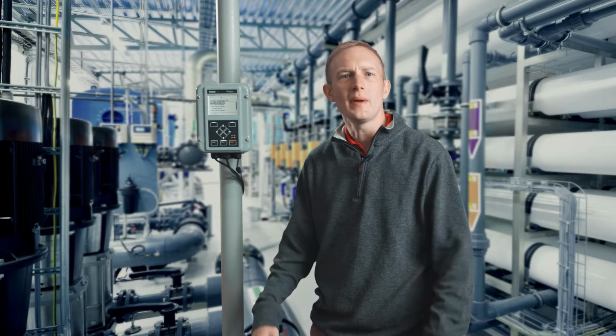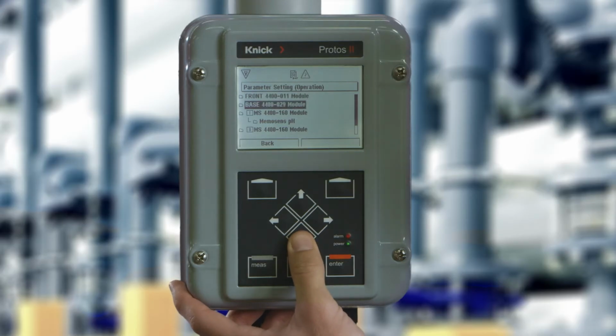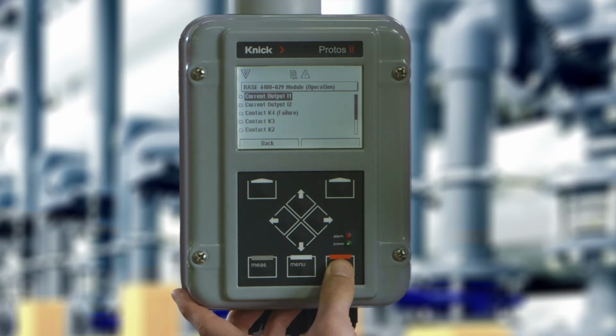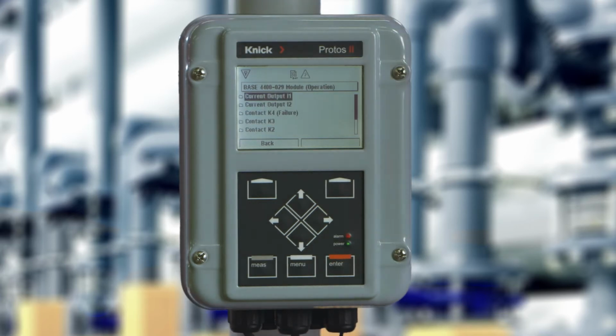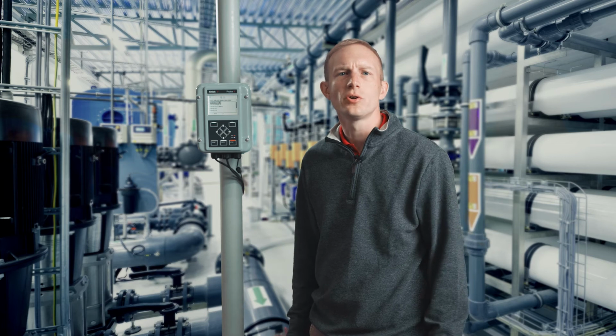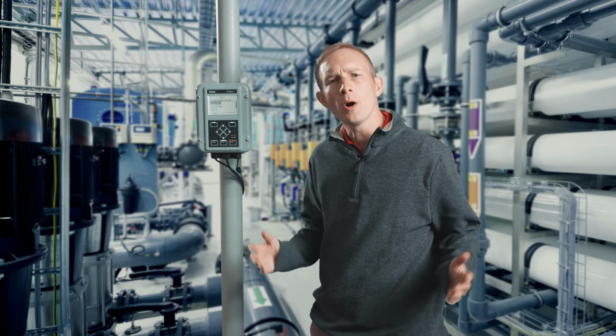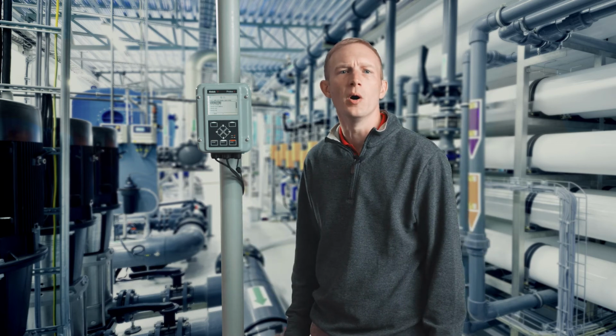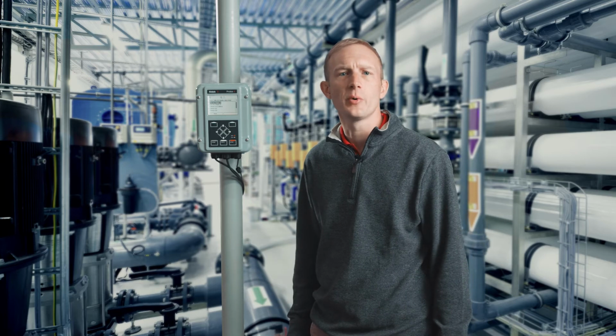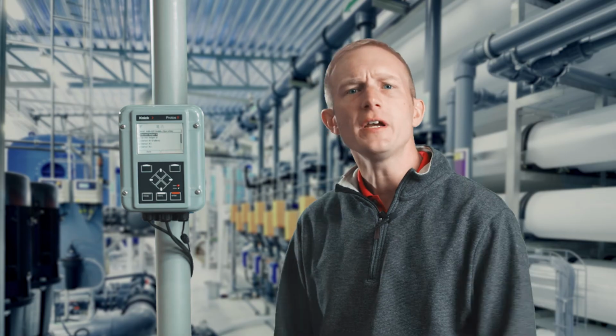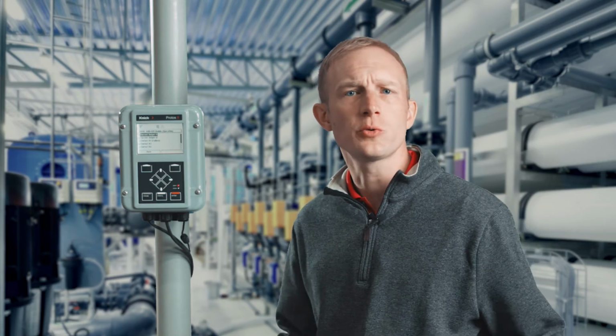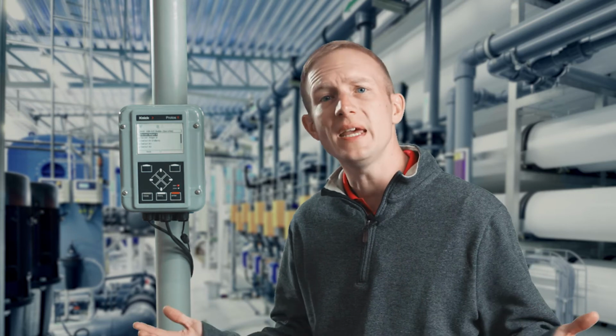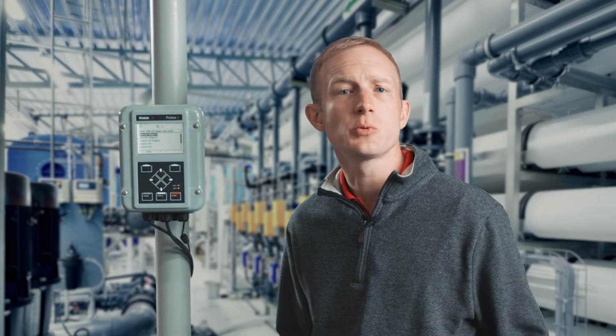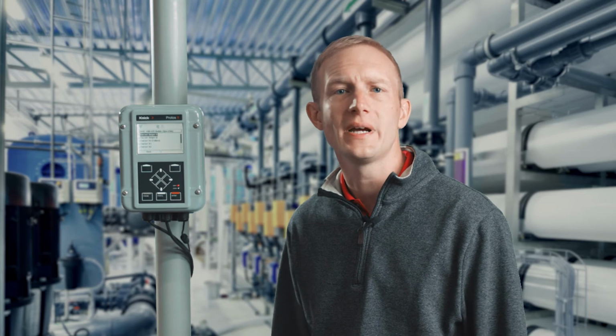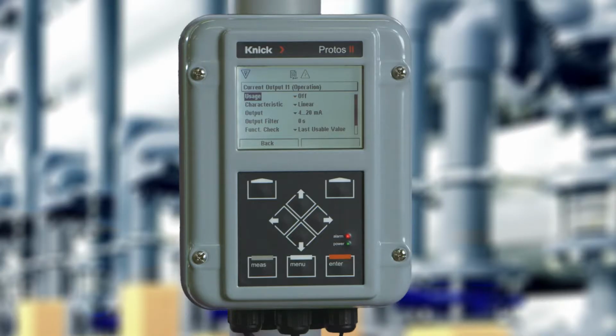Now, let's enter the menu for our base module and configure the 4 to 20 milliamp outputs and relays from the device. If utilizing any digital inputs for flow control or placing the transmitter into hold mode, they can also be configured within this menu. I'll configure the transmitter with 2 4 to 20 milliamp outputs for both pH and conductivity, as well as 1 low-level pH relay. As you can see, the output can be turned off if not in use.